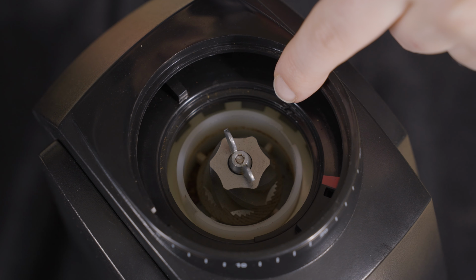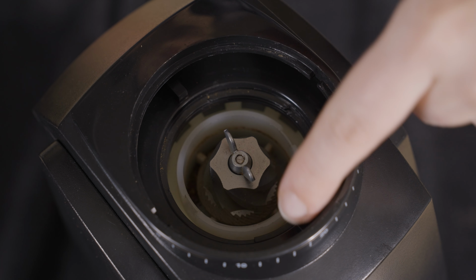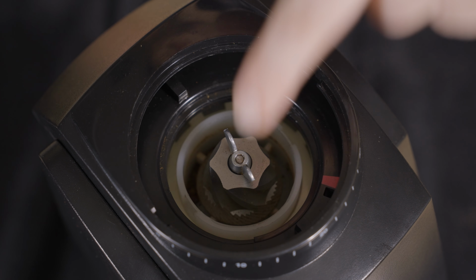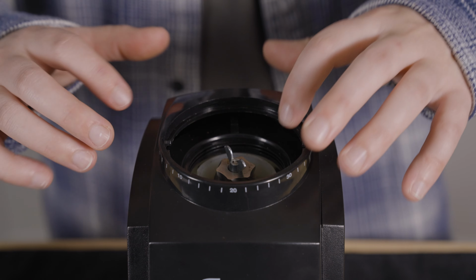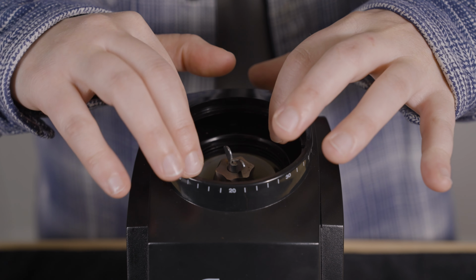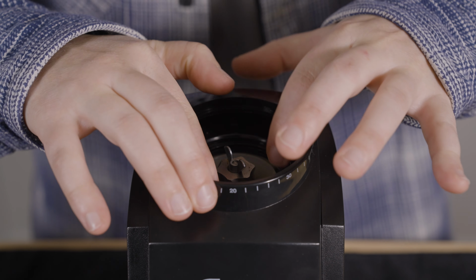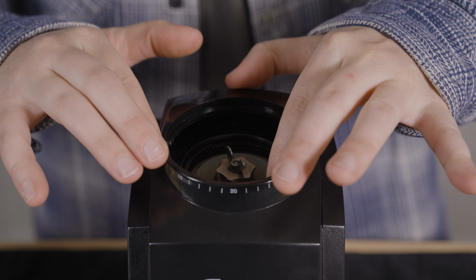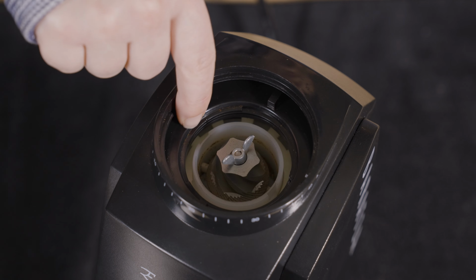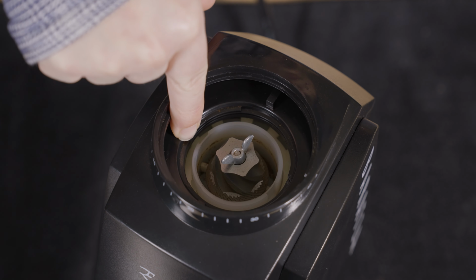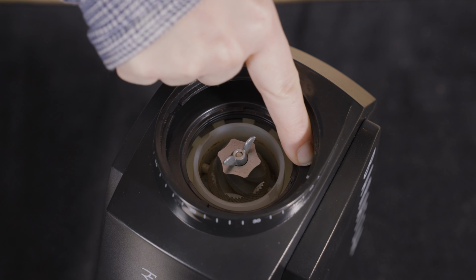With the rings inspected, we can perform a push-down test to check for damage to the calibration ring underneath. Press down firmly on the adjustment assembly at 2 points, alternating pressing with each hand. Your adjustment should stay firm. If you notice a wobble or feel it flex, it could indicate damage to your calibration ring.